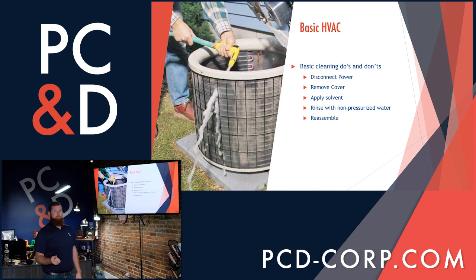Then we'll come back through with a water hose. Make sure that you either have just a light attachment as depicted here or just the hose itself. By all means, do not use any pressure device. Do not use a pressure washer, as that will damage the coils more so than do them any good. We'll start from the inside, again, as depicted, and work our way outside spraying the water. All the debris will be falling to the ground, and at the end of it, you simply replace the cover, screw it back into the cover, and then you resume power and turn it back on, either by the switch or the removable fuse.